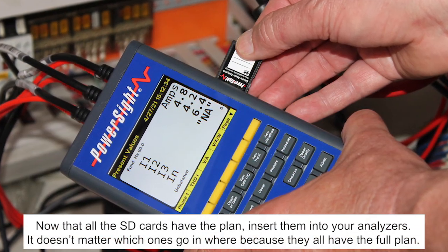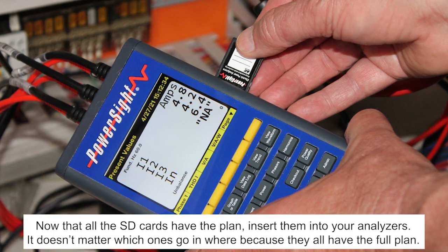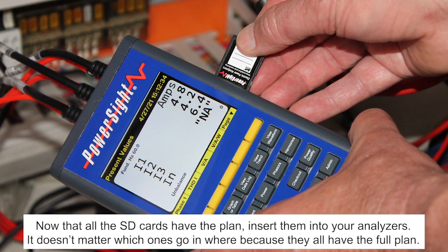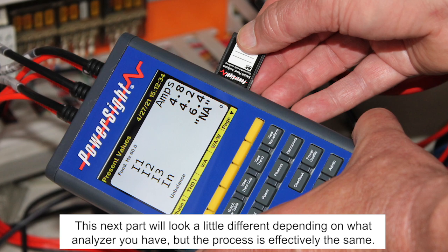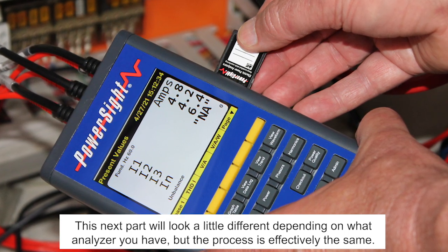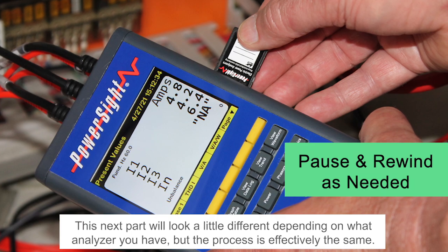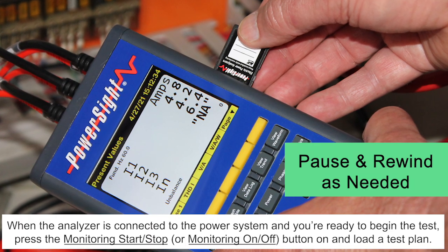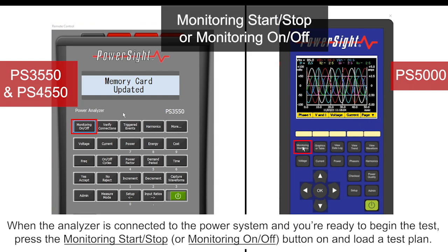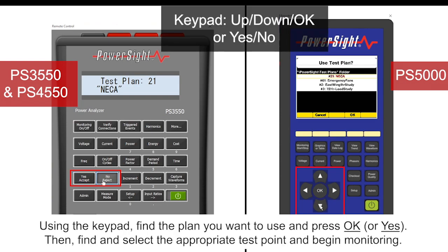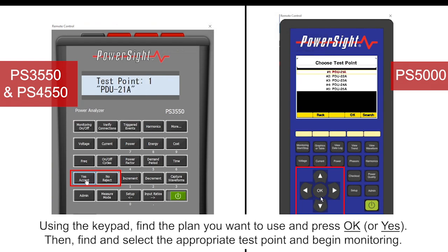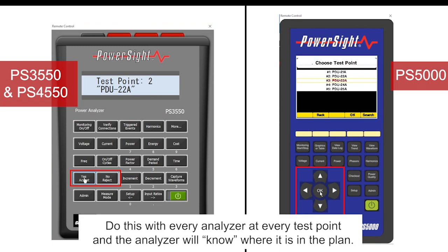Now that all the SD cards have the plan, insert them into your analyzers. It doesn't matter which ones go in where because they all have the full plan. This next part will look a little different depending on what analyzer you have, but the process is effectively the same. When the analyzer is connected to the power system and you're ready to begin the test, press the Monitoring Start-Stop button and load a test plan. Using the keypad, find the plan you want to use and press OK. Then find and select the appropriate test point and begin monitoring. Do this with every analyzer at every test point, and the analyzer will know where it is in the plan.